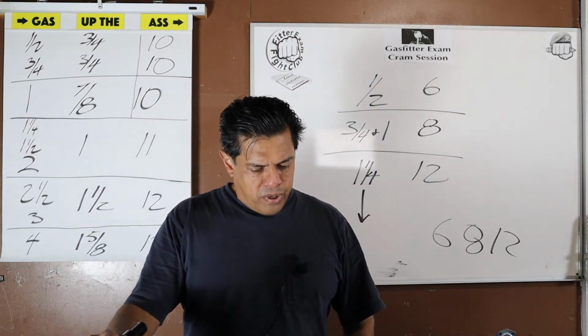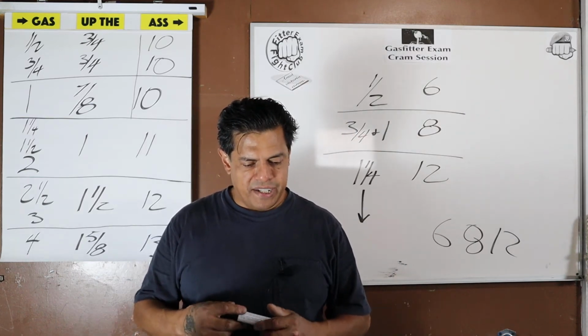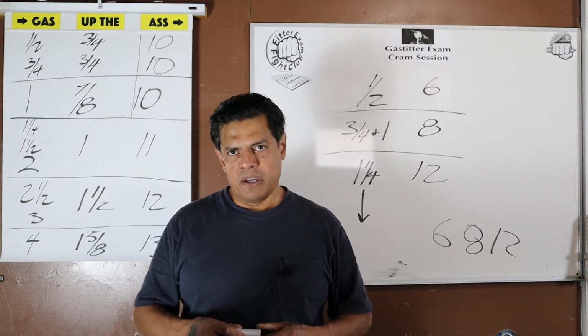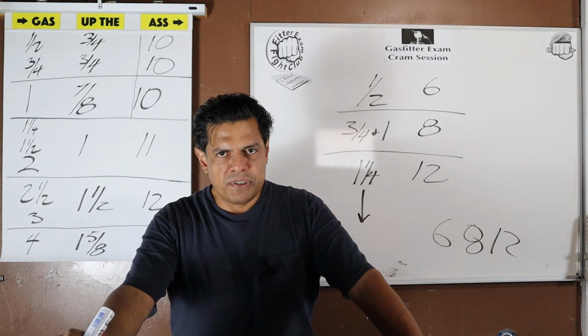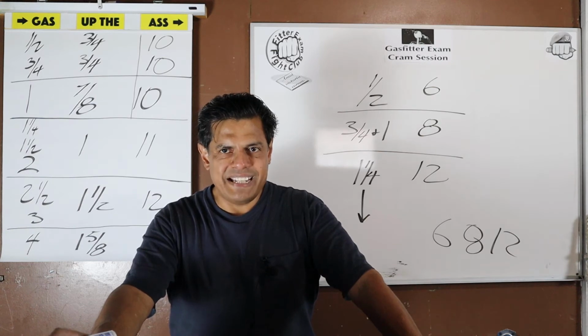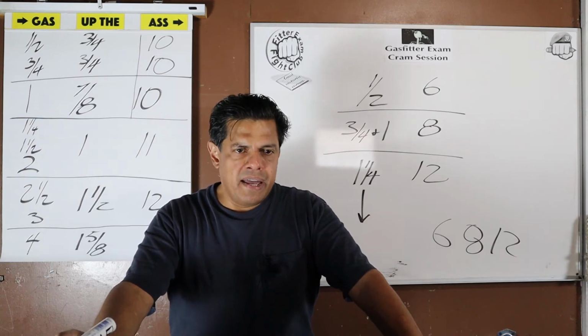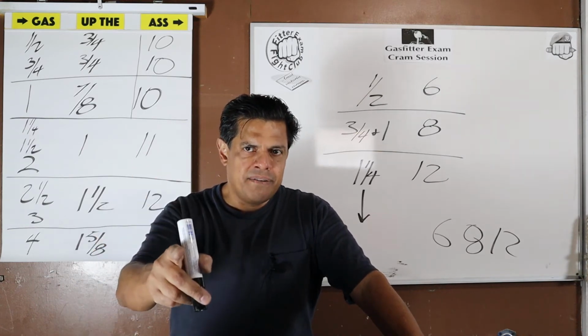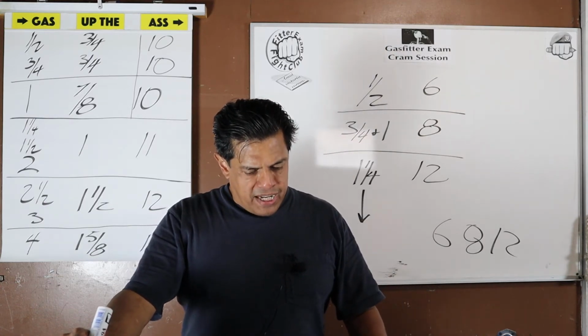Okay. Question 8. Gas service piping outside a structure shall be buried not less than, this is our blanket statement, not less than 24 inches below grade or 2 feet. Okay? And what was the one exception to that? We were allowed to go as shallow as 18 inches as long as we weren't running it under a driveway and we're protecting it from any kind of damage or freezing if it's wet gas. Okay? All right, question 9.